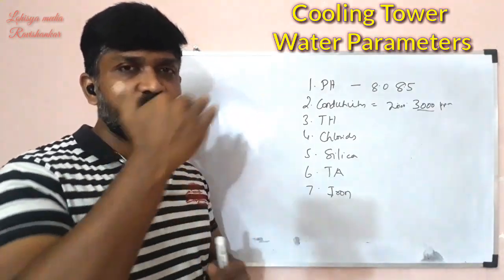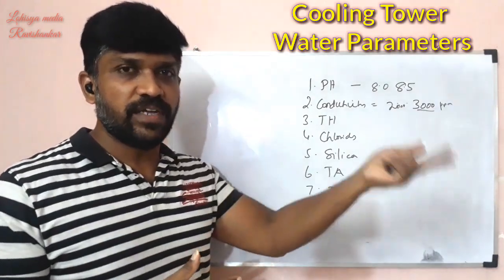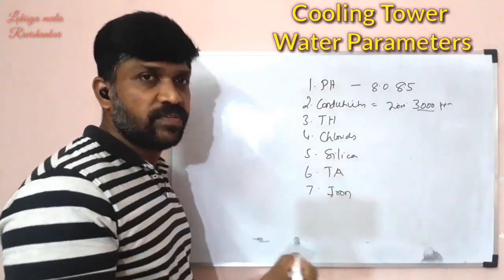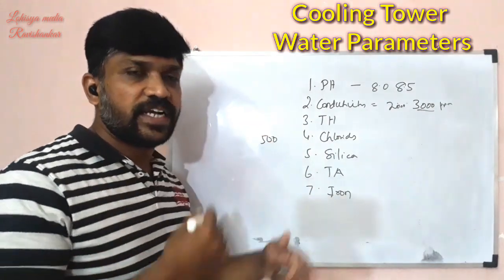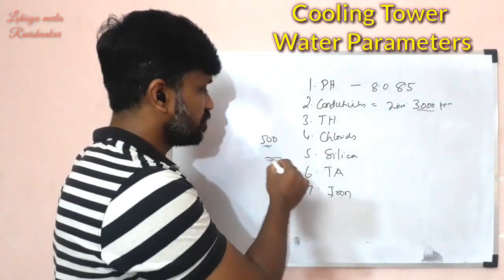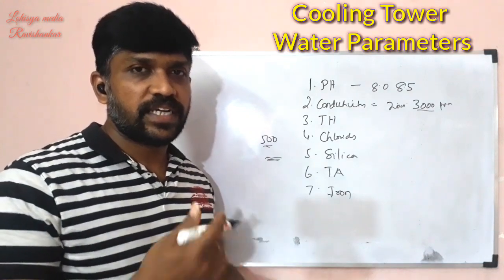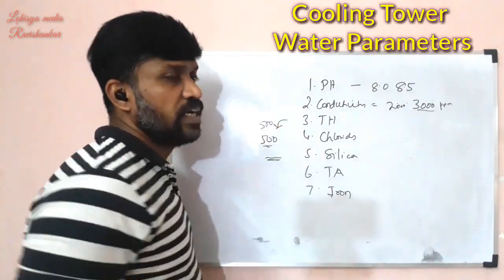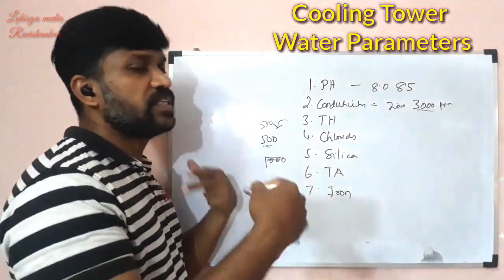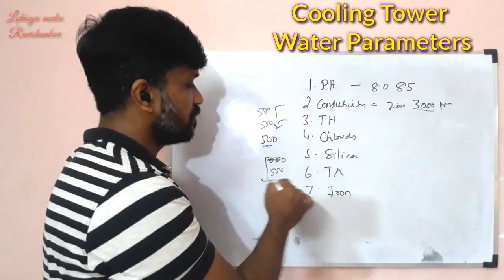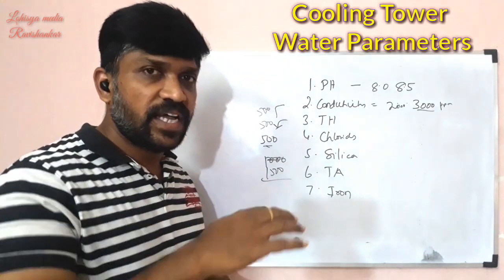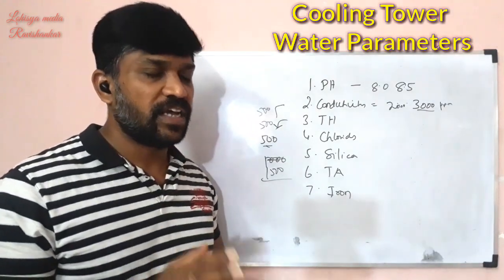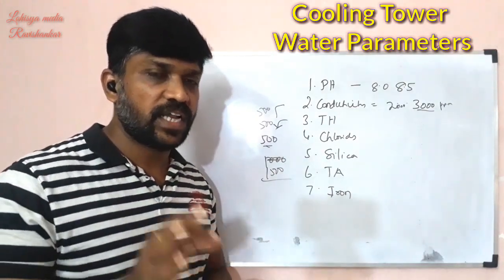If you have fresh water, evaporation will occur and you will have water losses, which you make up. Suppose the fresh water conductivity is 500. As evaporation occurs, the conductivity builds up — say to 1,000 — giving a COC of 2. The maximum conductivity we maintain is around 3,000 units, and we aim to keep it effective in the 1,000–2,000 unit range.